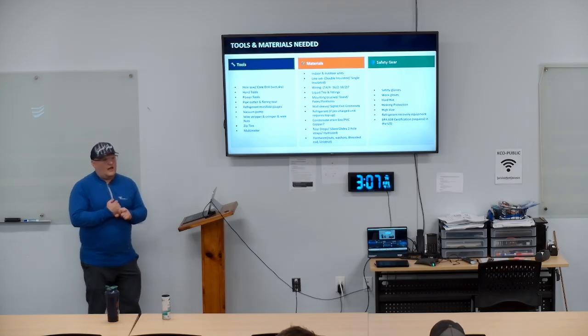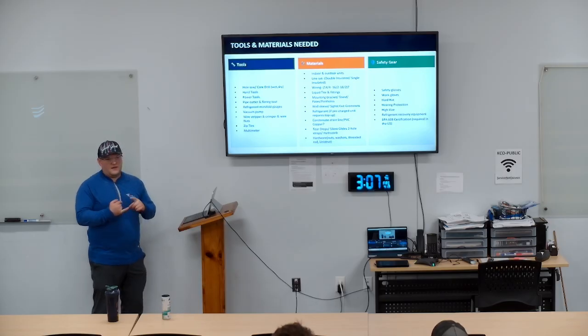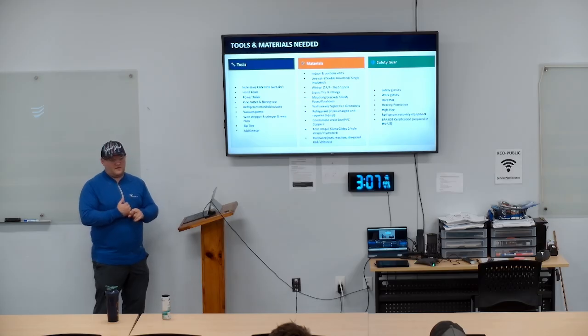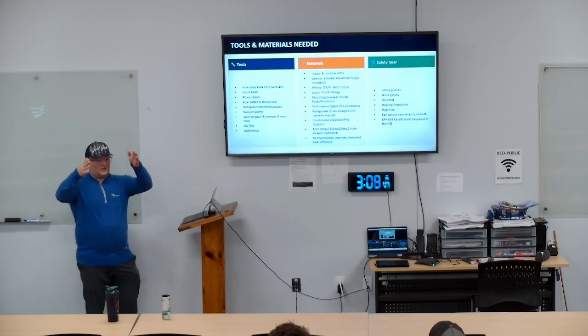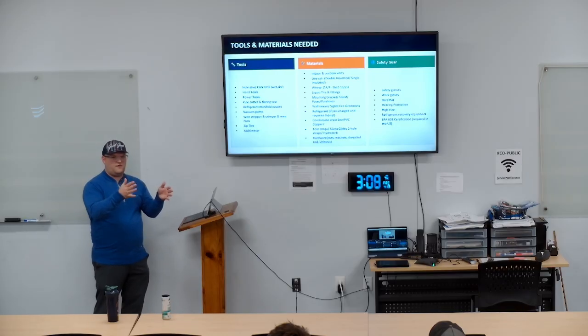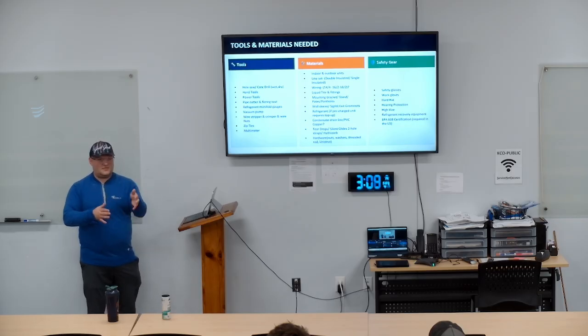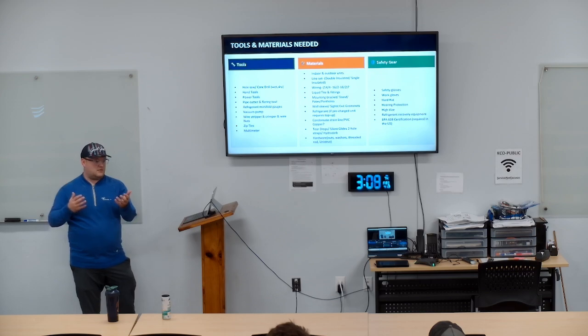The other thing you need to think about in line sets, honestly, line sets is one thing that I stress more about. So when we get a job from the PM, normally the first thing I do is go into the IOMs. I'll throw it out there, Daikin right now is probably one of the worst. When I say the worst, I mean they show port connections. It'll say 7/8, 3/8 on a 3-ton unit, and we can all just say, okay, cool, we're going to run 7/8, 3/8. Well, then you go to the IOM and they actually have a table laid out. If it's from 0 to 25 feet, you can run 7/8 to 3/8. If it's 26 feet to 49 feet, now it's 1-1/8 by 3/8.